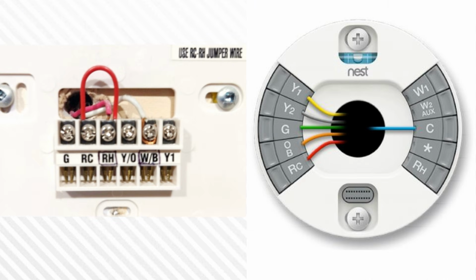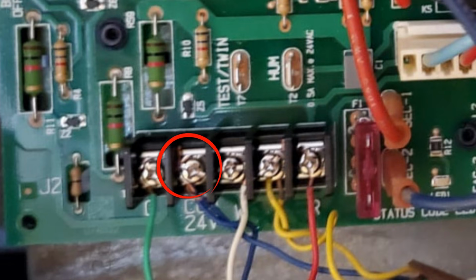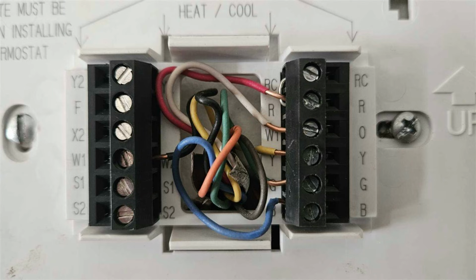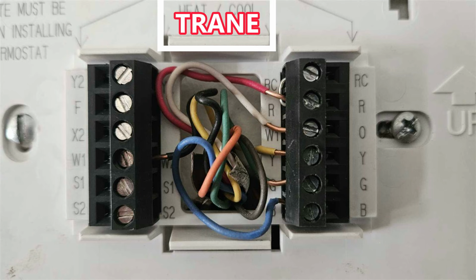Another common problem with the common wire is when the old thermostat didn't have one hooked up, you see an extra wire there, it's blue, you think it's common, you hook it up and it's still not working. The reason for this is because it's probably not connected at the other end at the control board inside the unit. Not all brands use the C terminal as a designator for the common. Trane thermostats, for example, often use B instead of C. So if you're upgrading from or to a Trane thermostat, just keep that in mind.